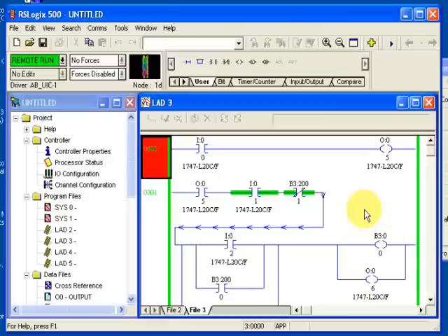And if I just go and operate the PLC, I might be able to get one of the inputs to go. So there we are. You can see input 02 going on and off there. That's it. So you're all online. But what you don't have is any comments. There's nothing written on the lines. That's because they're all saved on the original program, not in the SLC 500, but the original program written on your laptop or wherever it was written.